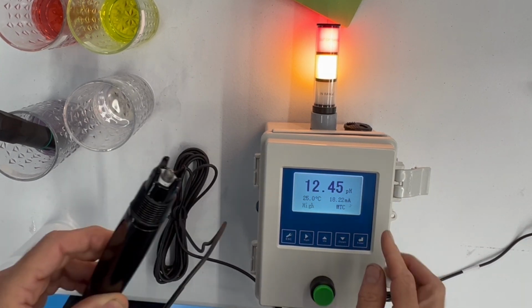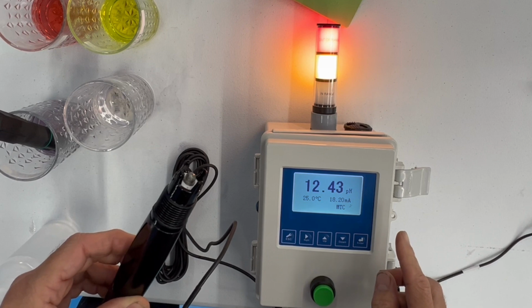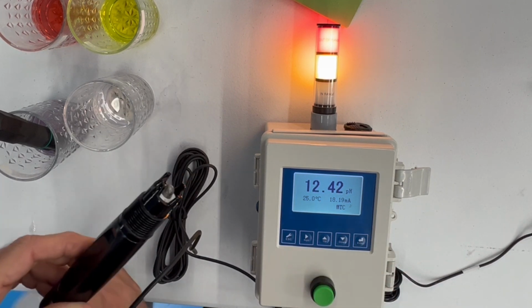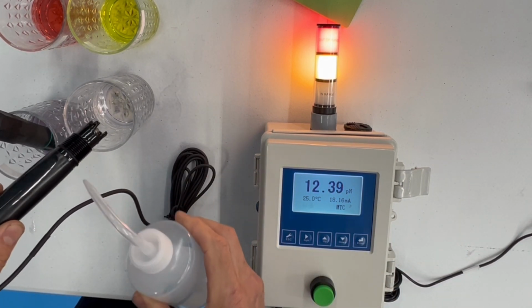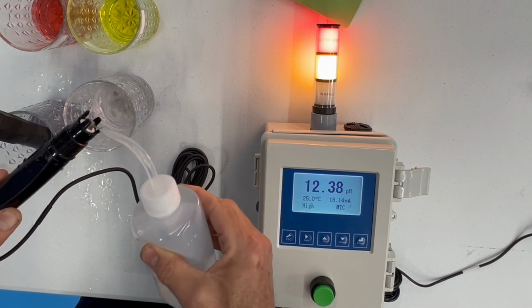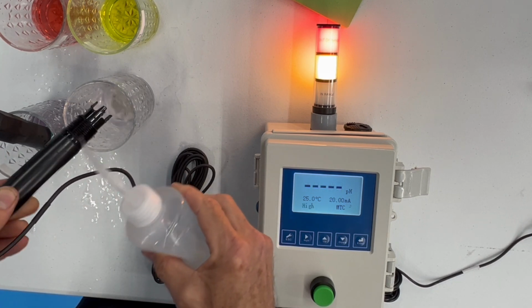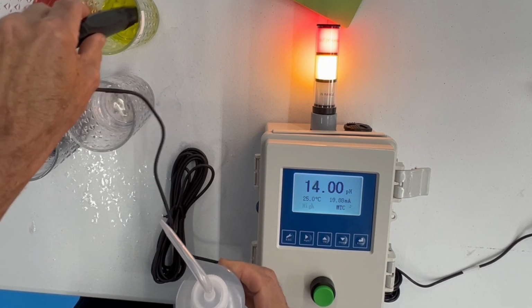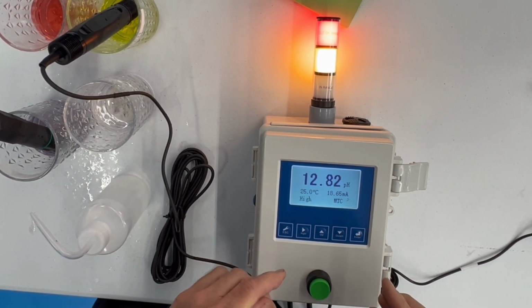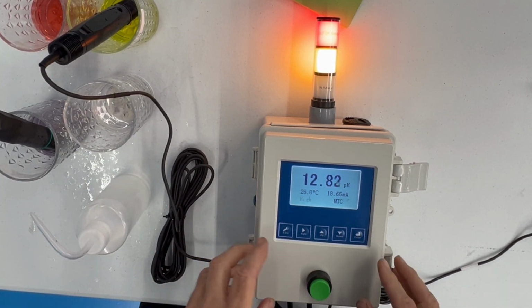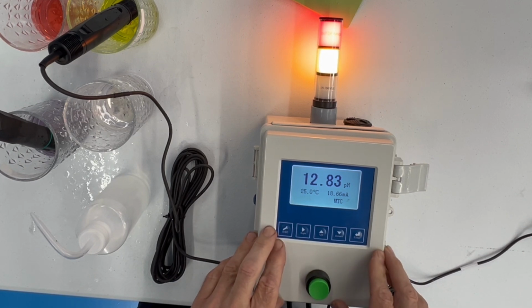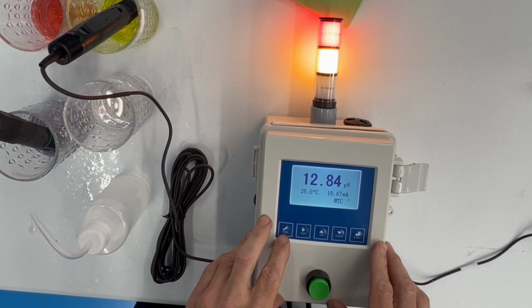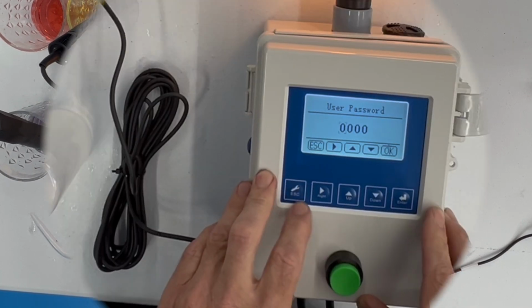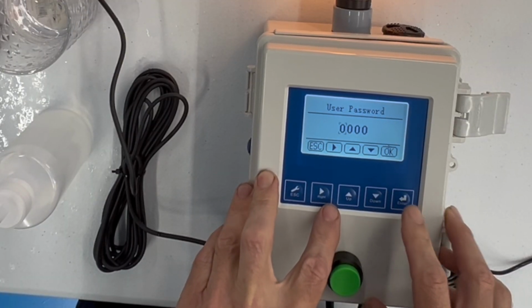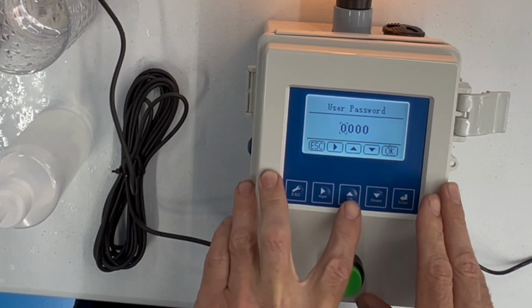This was calibrated previously to read 7 on a standard pH probe, but the reading is way off. Actually, let's put it in the 7 buffer. Because the electropotential across the antimony bulb is different from glass, the calculation by the pH controller is different, so we need to program it for the antimony probe.